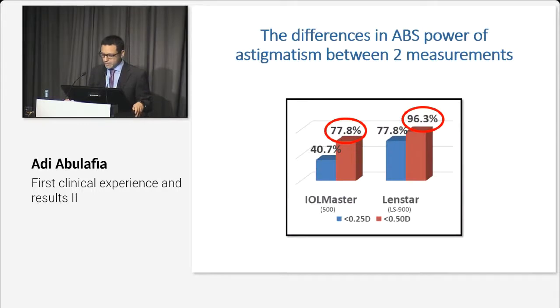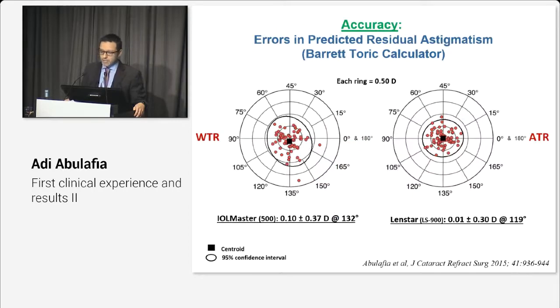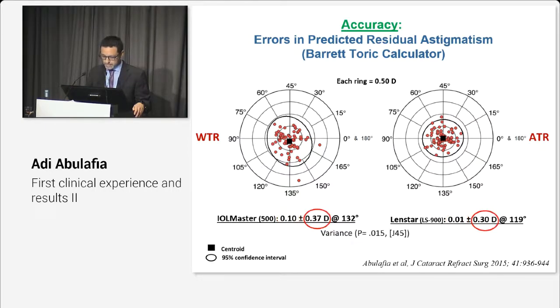The differences between the two measurements were below 0.5 diopters in more than 96% of eyes using the LENSTAR, as opposed to only 78% with the IOL Master. Looking at accuracy, here are the errors in predicted residual astigmatism following toric IOL implantation, and the LENSTAR had a significantly lower centroid prediction errors and variance as compared to the IOL Master.